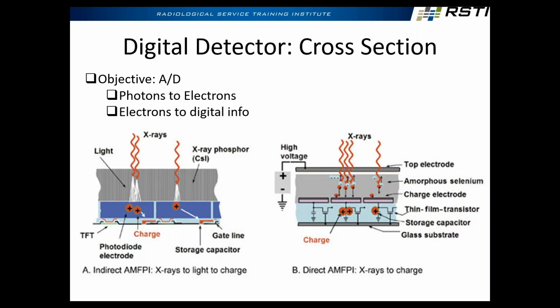It's a voltage, it's analog. It's a capacitor storing voltage. So how do we get to digital? Run that cap through an A to D, and it converts that number now to a digital number, which can be 8 bits or 10 bit or 12 bit or 16 bit, which we'll get to in a second. So this is indirect. Most detectors on the market use this. All Philips detectors, all Siemens detectors, all GE detectors. Pretty much everybody out there now has indirect technology. The only manufacturer really using this widely is Hologic with their MAMO, with the direct detectors.